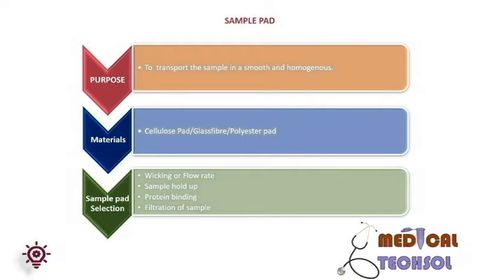The sample pad's function is to absorb and transport the sample in a smooth and homogeneous manner. It should retain very little sample. General materials used are cellulose, glass fiber, or polyester pad. Factors considered for sample pad selection are flow rate, sample holding volume, protein binding, and filtration of the sample. Filtration is aided by adding protein, detergent, or salt to reduce non-specific binding, increase sample viscosity, change pH, and filter red blood cells (RBC). This is achieved by adding an agglutinating agent into the sample pad. Treatment is usually done by dipping or spraying followed by drying.